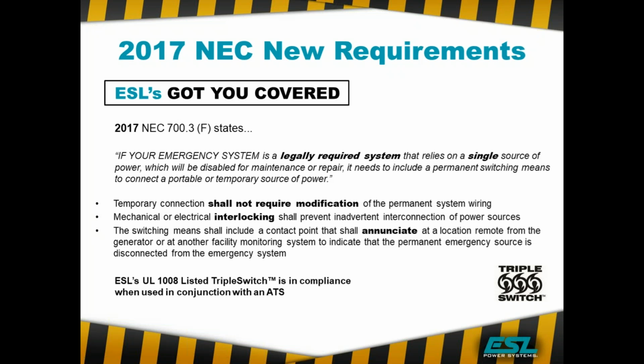And most of the time you would think about a hospital. They're legally required to have generators. Now, they don't typically fall under this code because most hospitals will have multiple generators, so they have backup to the backup. However, there are a lot of medical facilities, smaller hospitals, clinics, rehab facilities, dialysis, other types of medical facilities that only have a single source permanent generator. So they would be legally required to have some sort of backup for that permanent generator.